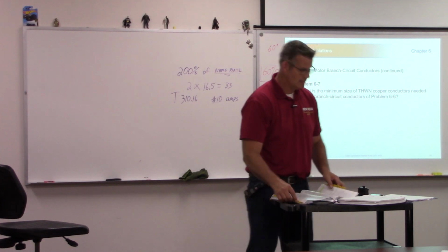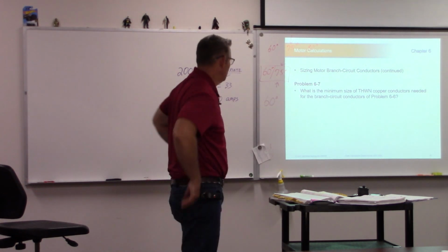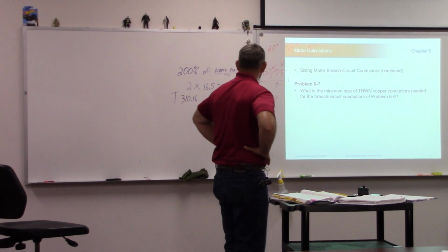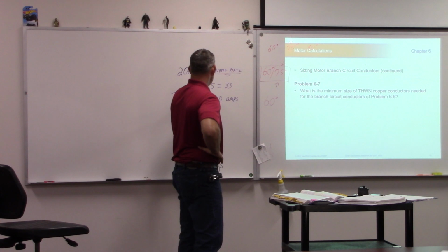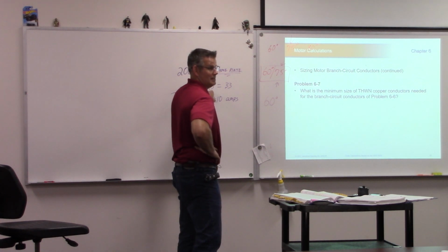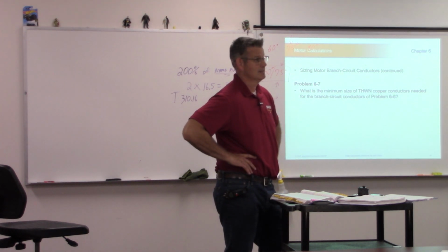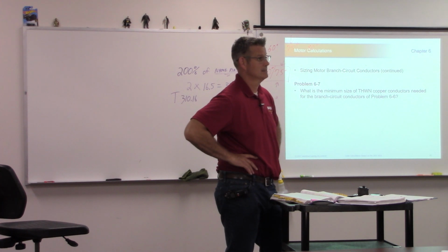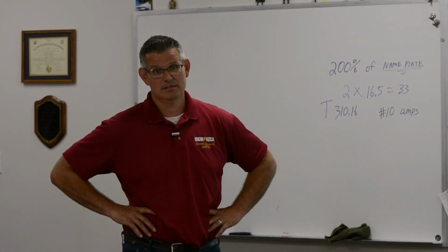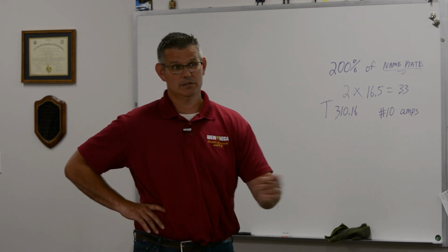Depending on the distance that the circuit's running, right? Yeah. And this is why I say I wouldn't have a problem using 10s. What is the motor actually drawing? 16 and a half amps. You see that? Do you feel more comfortable with the number 10s? The only reason you're sizing it for that is the varying duty that's happening, right? That varying duty is probably throwing that motor into frequent overloads, which is running this amperage up.